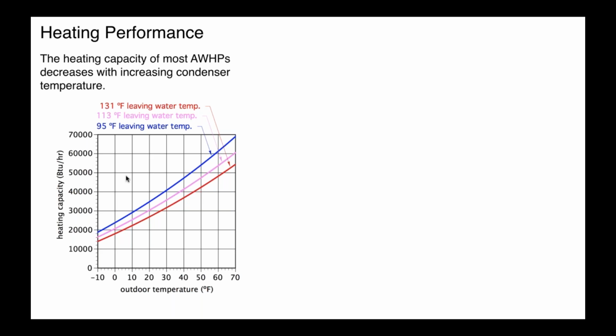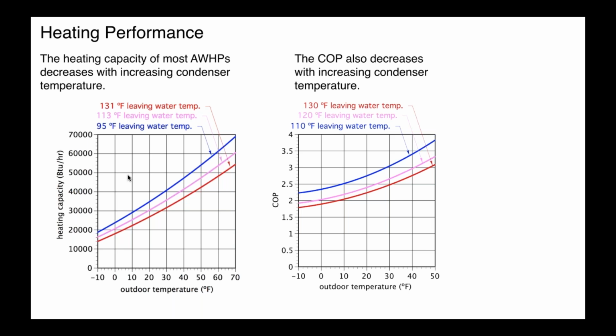It tells you that low water temperature distributions are really important to get the best efficiency out of air-to-water heat pumps. It's the same story with geothermal water-to-water heat pumps. It's the same story really with any heat pump, because anything you can control that can bring those temperatures closer together between the source temperature and the load temperature, the better the performance.